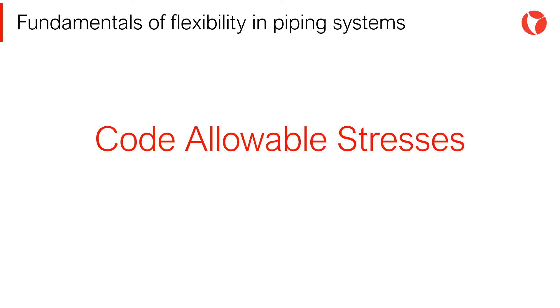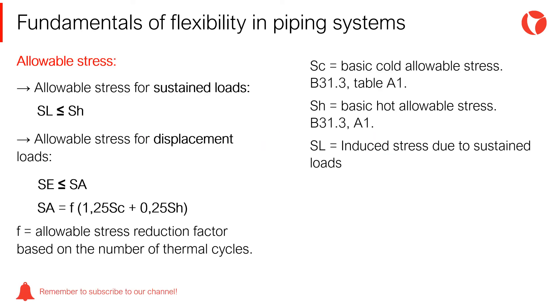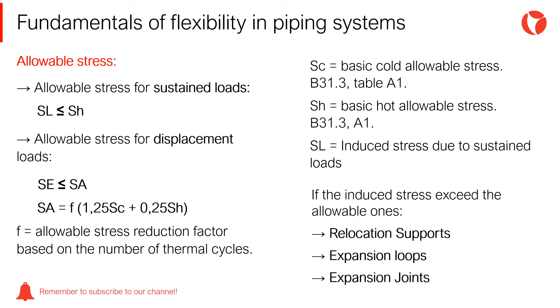The allowable stresses of a piping system are determined based on the design code used. In this case, the ASME B31.3 code has been chosen to give the explanation, since it is one of the most restrictive and with the greatest use and application across many industries. It is worth mentioning that the allowable stresses used in other ASME B31 codes follow the same criteria. For each type of load and induced stress, there corresponds a type of allowable stress. If the induced stress exceeds the allowable ones, we have to relocate supports, use expansion loops or expansion joints.